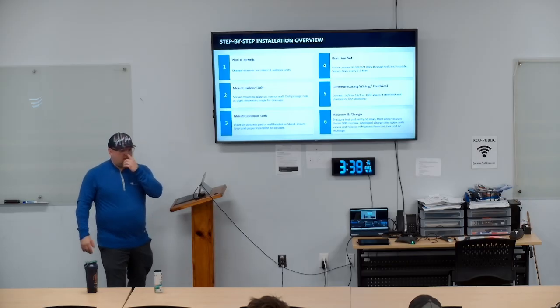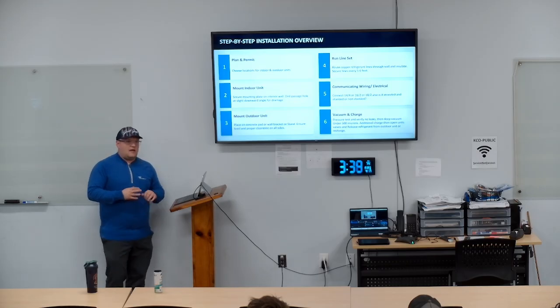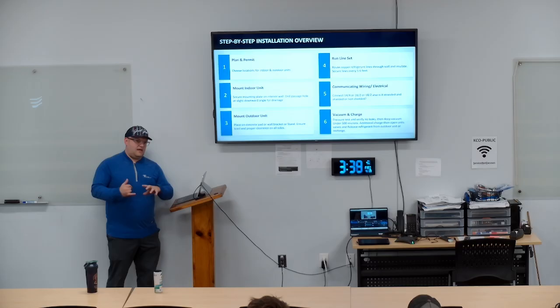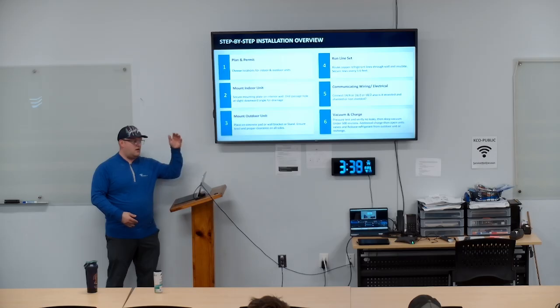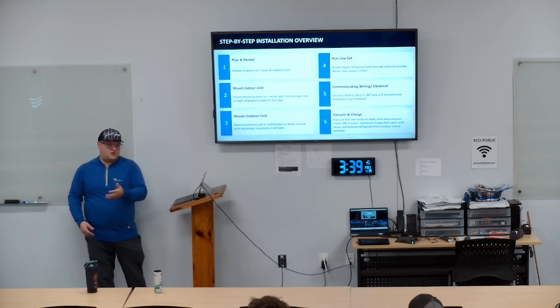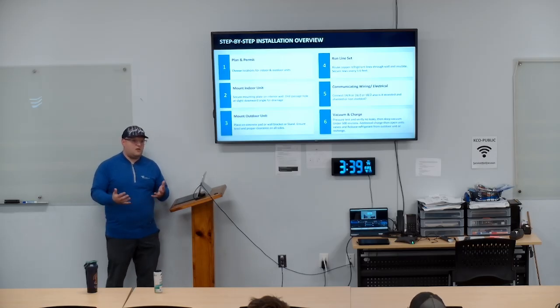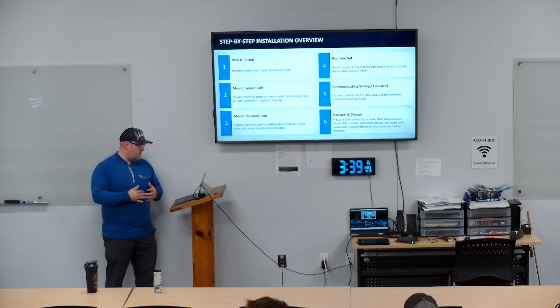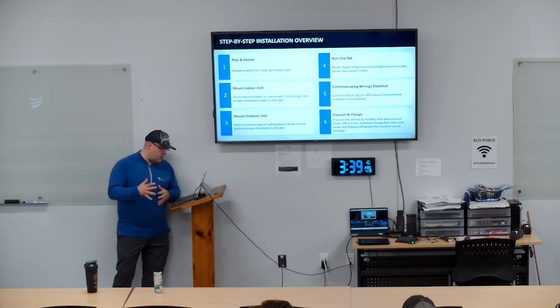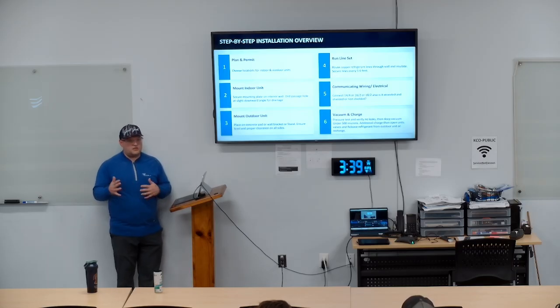I can't stress the importance of that because if you don't have a pressure test and you get to the end of a job, normally at the end of jobs, it's go, go, go. We got to start this unit, got to get it going. Commissioning, we've set up a commissioning for this day, needs to be done. Pressure test has to hold. Okay. Vacuuming, charging, you're not going to achieve a vacuum without a pressure test. It just ain't going to happen.